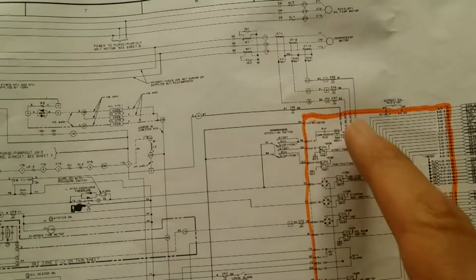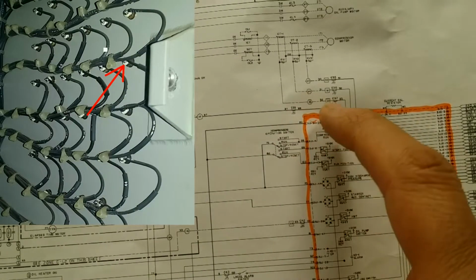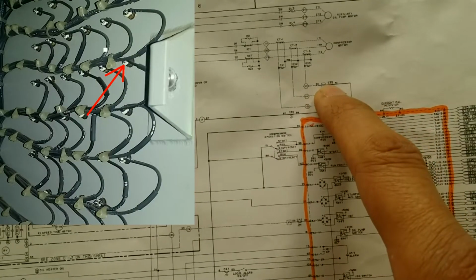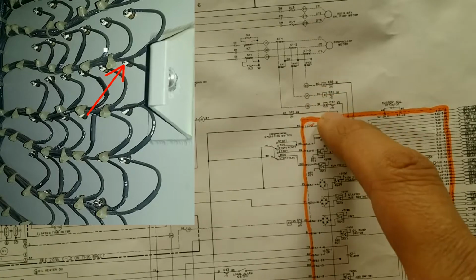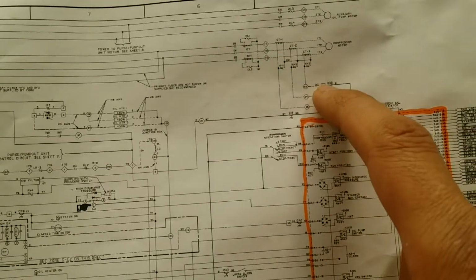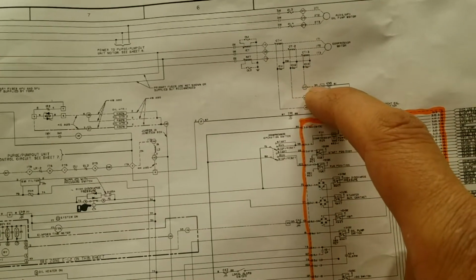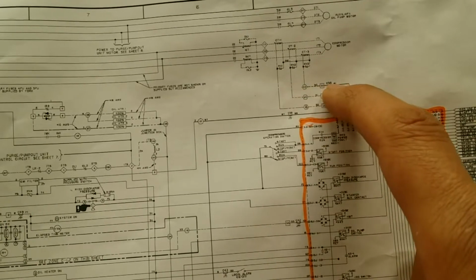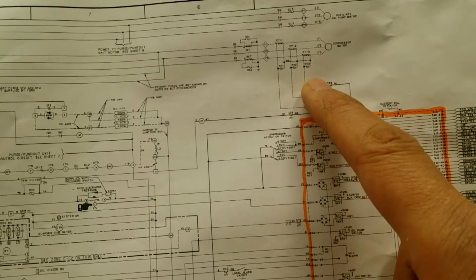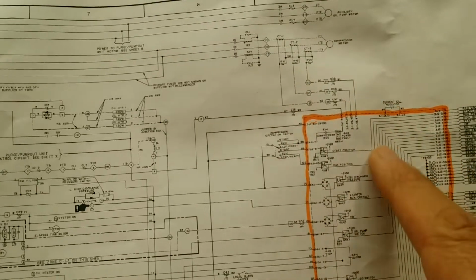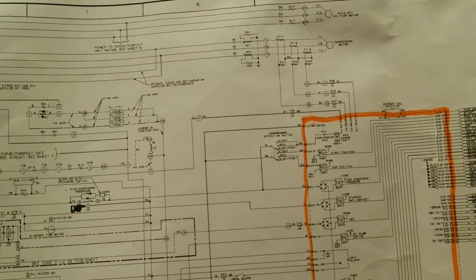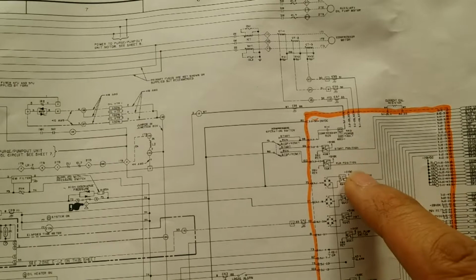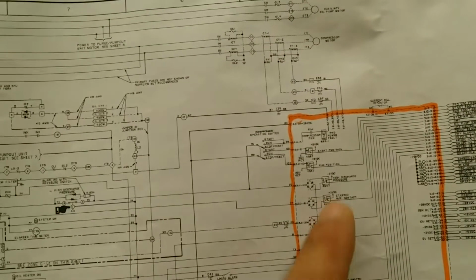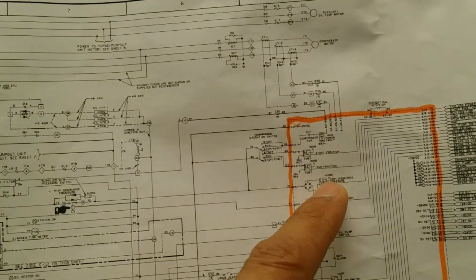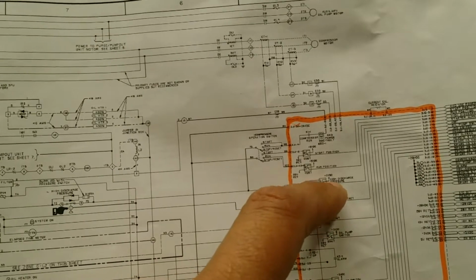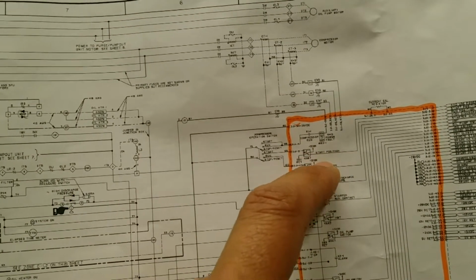Now, all signals that go into the cards, or the majority of them, go through what's called a feedthrough capacitor, and that's what the symbol is in there. So the signal that goes through it is not supposed to be grounded, it's supposed to go through it, and all the harmful high frequencies stay on the outside and don't make it to damage our circuit cards. These circuit cards are very delicate, and even if you open the panel and use your radio to talk to somebody in front of the circuit cards, you can fry them. That's how delicate they are.